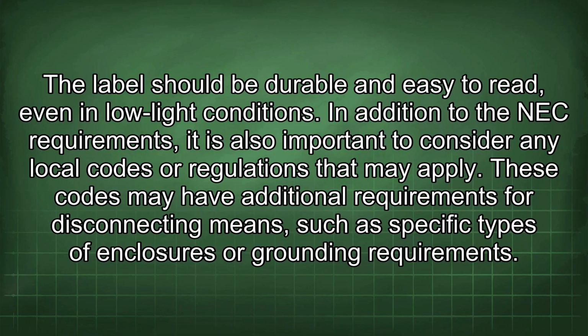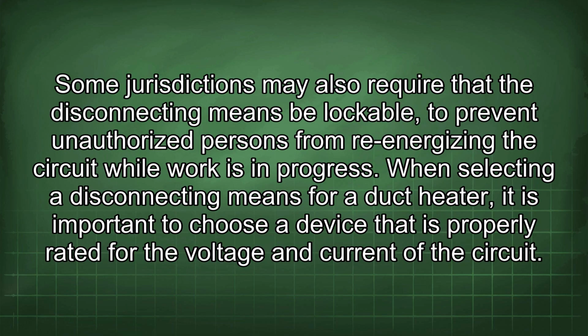In addition to the NEC requirements, it is also important to consider any local codes or regulations that may apply. These codes may have additional requirements for disconnecting means, such as specific types of enclosures or grounding requirements.